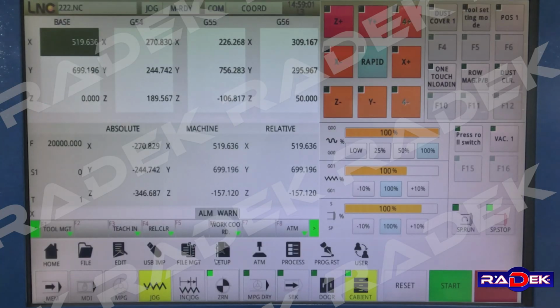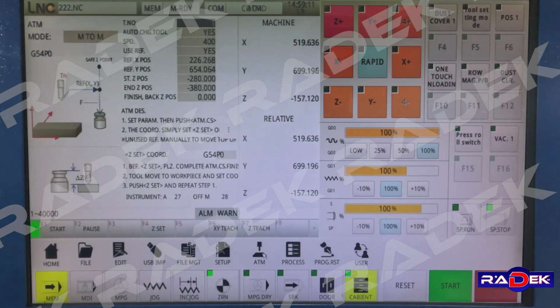A main indicator for successful zeroing of the axes are their coordinates in the field absolute, where their values should be 0.000 for both axes. Next step is to set up the origin point for the z-axis, and before we do that we need to turn on the vacuum pumps.